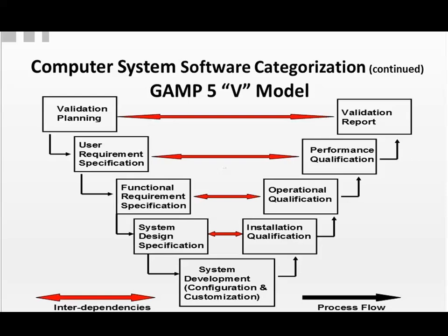You then develop your system, customize it, or configure it. Or you could have a system that's basically out of the box and is not customizable or configurable. Based on that, you want to be able to classify your system, categorize it, and be able to do your validation level of testing that's appropriate. Your IQ has to be done for every bit of hardware and software. You want to make sure you're installing everything properly. Screenshots or a video recording of the process of installing software, for example, should be considered for your documentation.